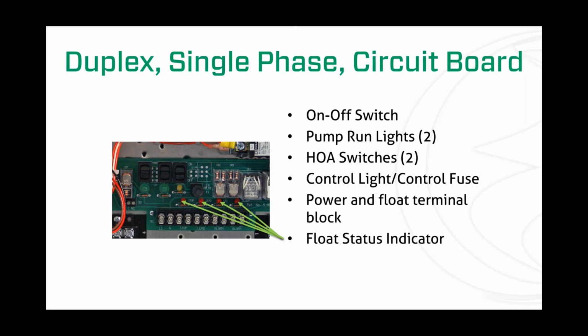I could open up the control panel and have some idea where the water level was going to be when I opened up the pit, just by looking at those lights. Also, if you ever had a bad float switch, you might simply look at that light and see that one of your float switches didn't come on. So you might know your float switch is bad by those. Really handy little things.